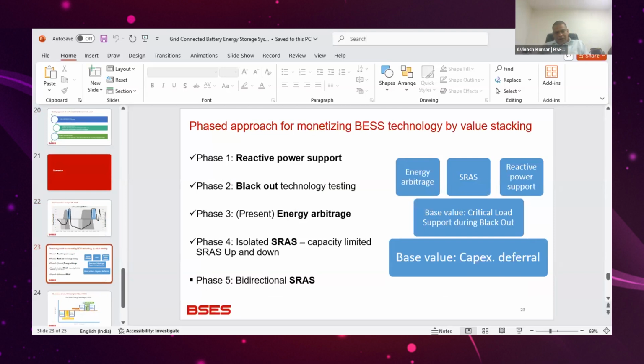When we talk about the use cases of this battery energy storage system, the base use case is of course capex deferral, because the PTR is going to be overloaded during the peak period, and the CAGR in that area is nearly 7%. So we avoid installing another power transformer for a short-duration peak load, and we utilize this battery energy storage system to meet the peak demand.